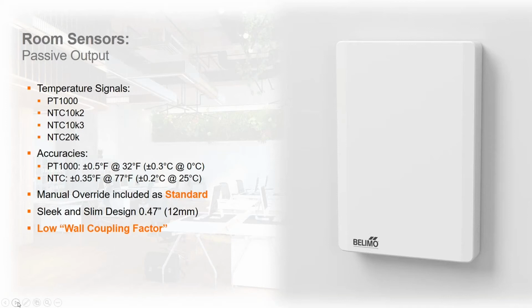One big thing with room sensors in general - they're measuring the actual occupied space, where the people are residing. So accuracy becomes extremely important. With our PT1000 sensor, we're at plus or minus 0.5 degrees Fahrenheit accuracy, and on the NTC thermistors, we're down even below half a degree Fahrenheit, into plus minus 0.35 degrees F, which is great accuracy for room type measurements.